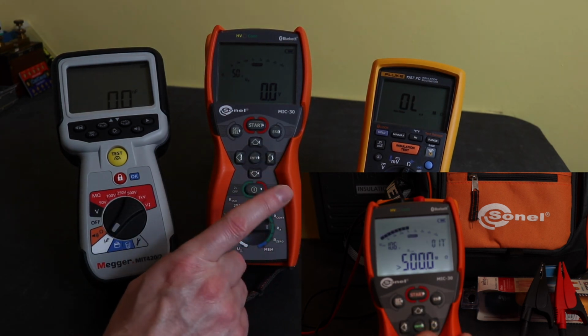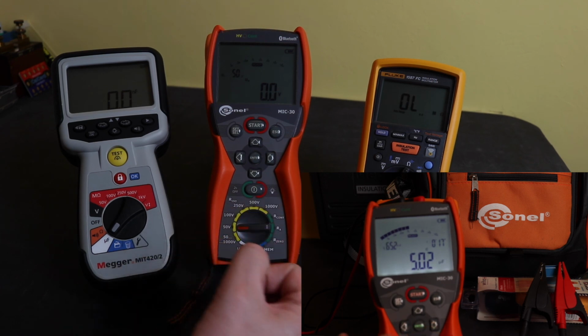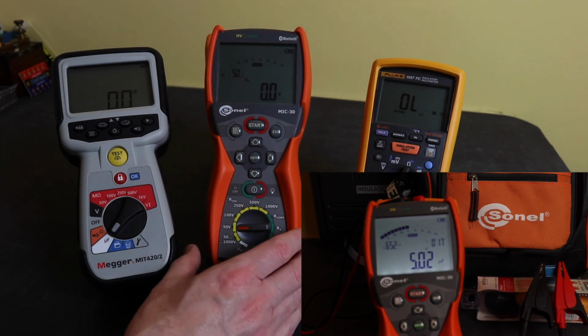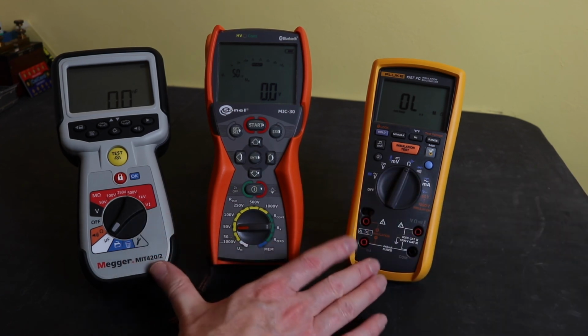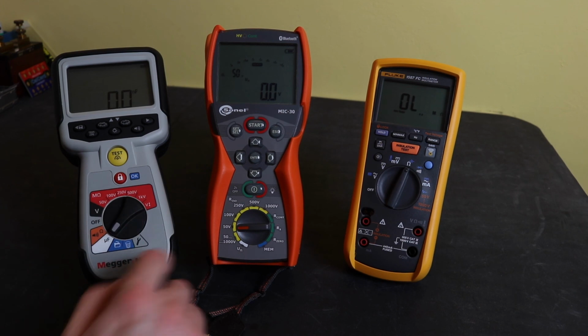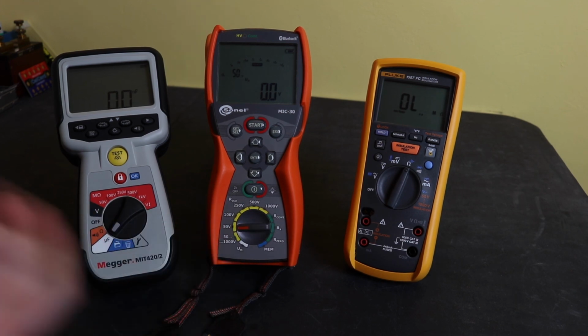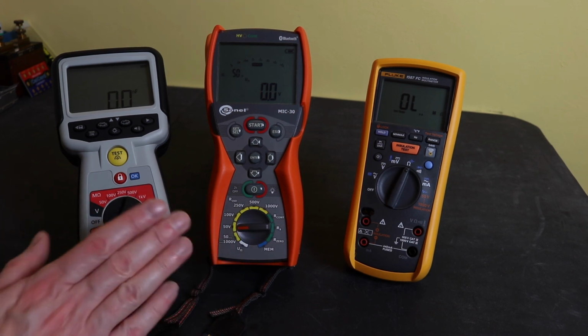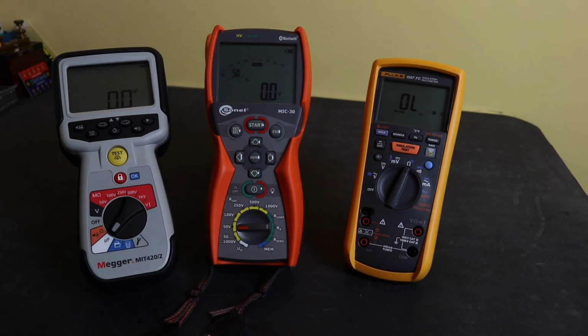The other problem is, because you're doing it on the insulation and you're effectively charging up the capacitor, it takes much longer to do a capacitance test on this instrument than it does on either the Fluke or the Megger, because you have to wait for this to settle. So it is there, but it's not as user friendly as these other two instruments.